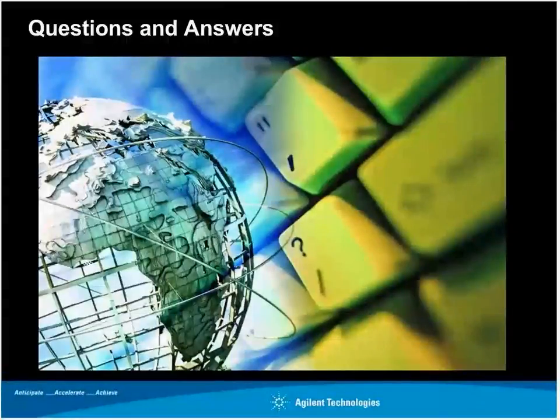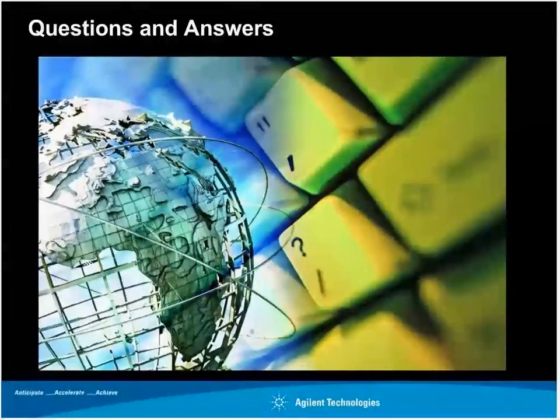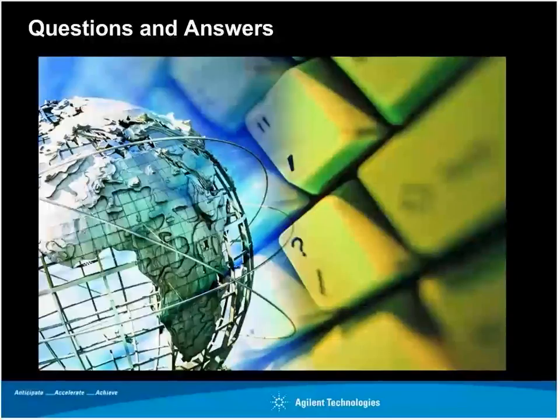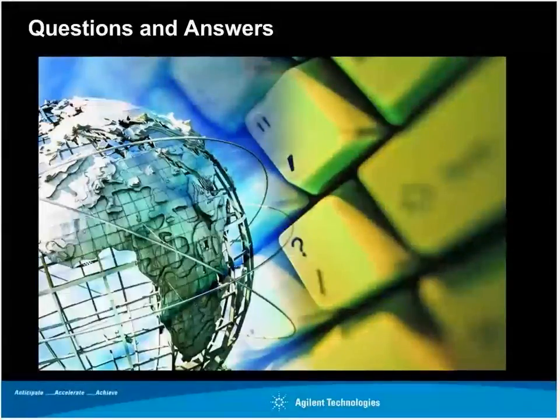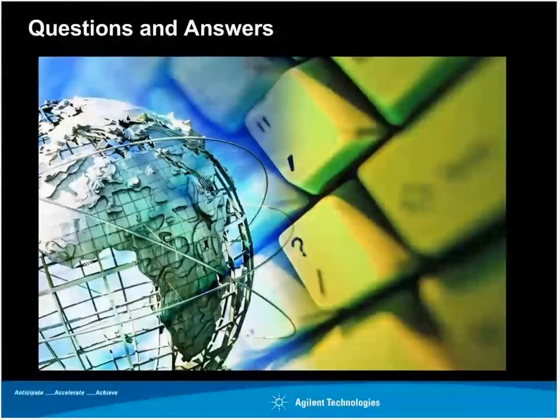So real quickly, when you're developing a calibration test procedure, as part of that effort, for the measurement uncertainty, you're identifying what all the sources of error are, then you're quantifying them, and then finally you're combining them. Well, if you don't change the test procedure nor change any of the test standards, you can go for many years with the same measurement uncertainty. But as soon as you change the procedure or any of the test standards, then you need to go back and revisit that and see which terms change and do an update.